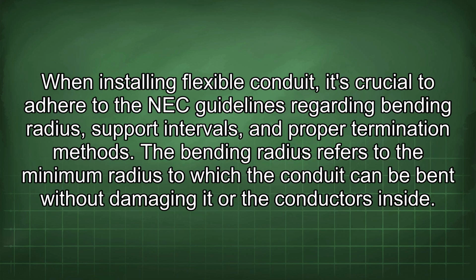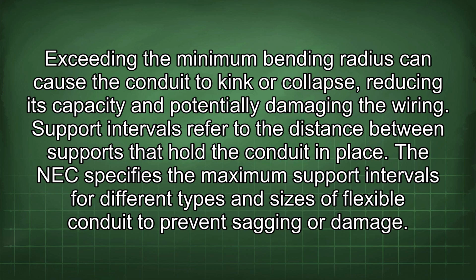When installing flexible conduit, it's crucial to adhere to the NEC guidelines regarding bending radius, support intervals, and proper termination methods. The bending radius refers to the minimum radius to which the conduit can be bent without damaging it or the conductors inside. Exceeding the minimum bending radius can cause the conduit to kink or collapse, reducing its capacity and potentially damaging the wiring. Support intervals refer to the distance between supports that hold the conduit in place. The NEC specifies the maximum support intervals for different types and sizes of flexible conduit to prevent sagging or damage.